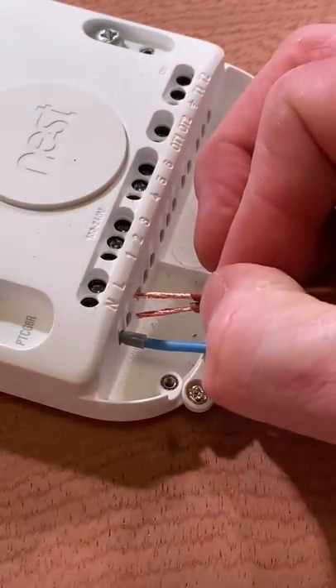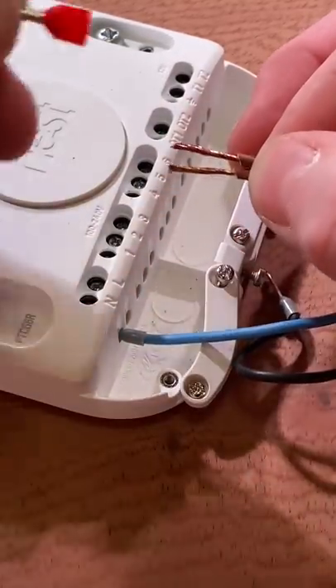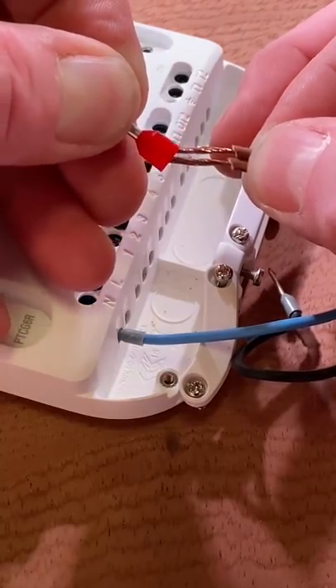But what if we had two conductors? We're not even going to attempt to put two in there — we're going to introduce a double ferrule. Note the conductors aren't twisted together; they're simply slid in side by side into position.